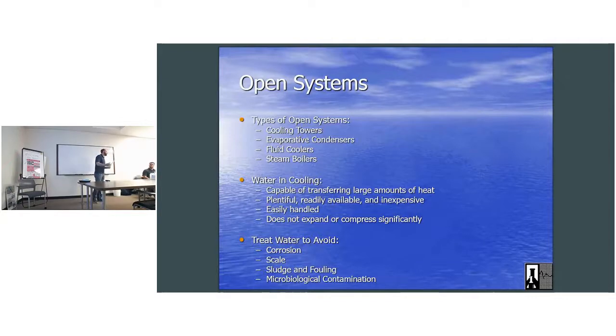My first question is, do any of you have current water treatment problems, or have had them? Like towers that don't work because of treatment problems. I've had several. I used to do a lot of startups on a Climate Cool chiller. It's got a brazed plate heat exchanger with a 60 mesh strainer, and they're really stringent on their water standards. I've had several issues where we've installed them in older buildings, and the strainer plugs up in 3 seconds. Did they flush the older loop before they put the new chiller on? Yeah, they did. They spent like $15,000 with U.S. Water on a treat and cleanup project, but they couldn't get it clean. So we ended up doing a plate and frame to separate everything.